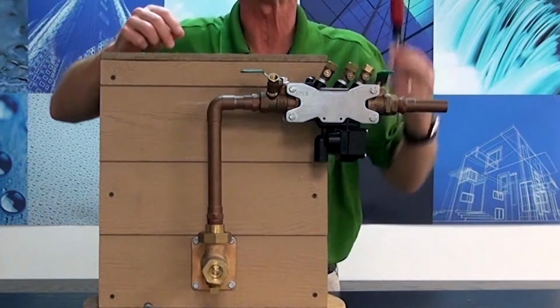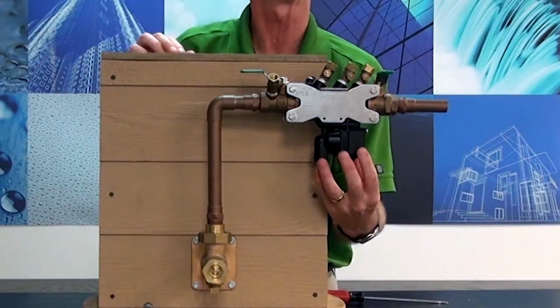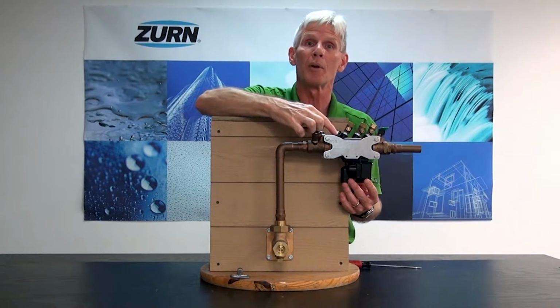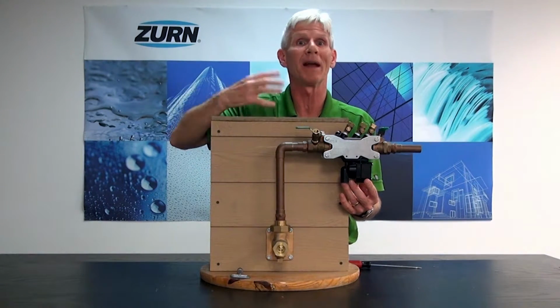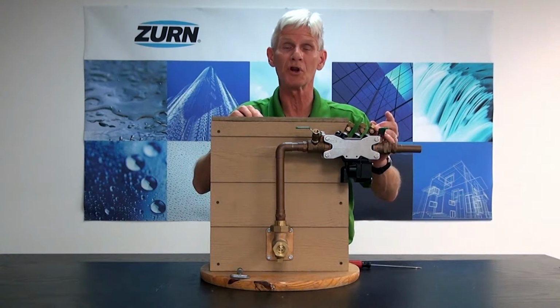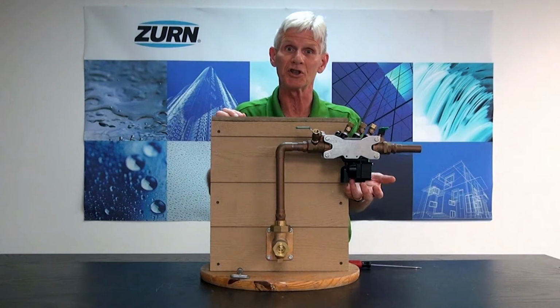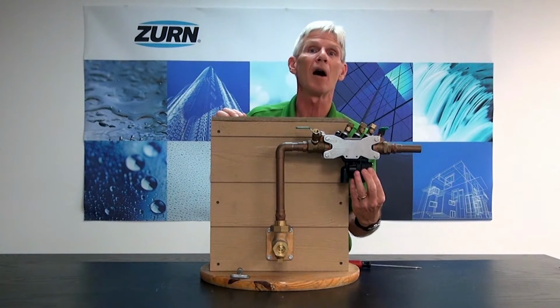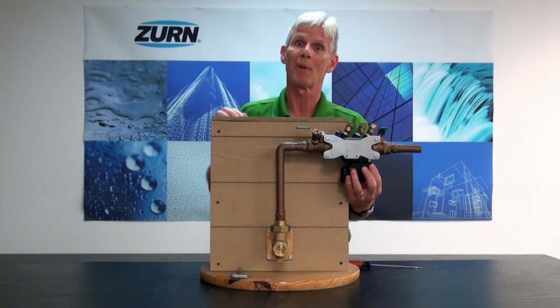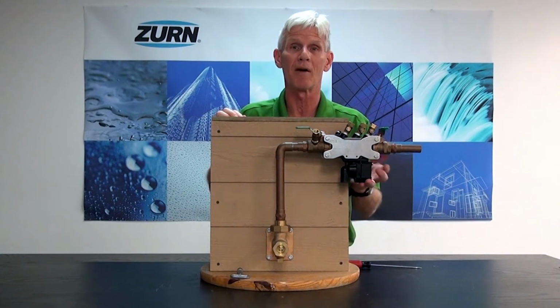When I open up test cock number 4, and while it's flowing, if my relief valve discharge diminishes or ceases, I know I have a fouled number 1 check, and I need to correct that by cleaning it up or replacing the rubber. Lastly, while test cock number 4 is open, if I see no change in relief valve discharge, that tells me that the relief valve proper has a problem, most likely fouled with debris, and I want to shut in my backflow preventer and clean up the relief valve accordingly.